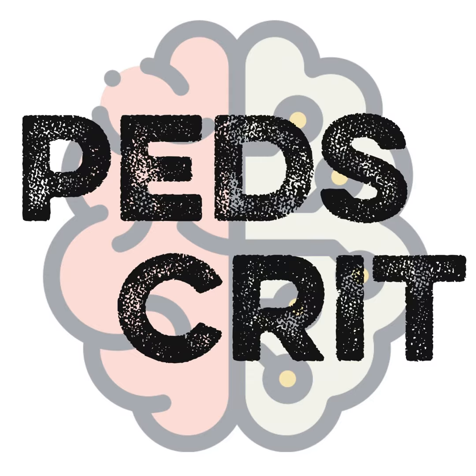So if you nebulize things like mucomist or DNase or antibiotics, all of those things, the diluent tends to be in glycerol. And glycerol tends to be sticky. And a device that's supposed to slide with minimal friction, that doesn't go well together. So patient with cystic fibrosis, you're trying to do mucomist and pulmozyme, and you need them on the VDR. Our standard is that for a patient that's not getting any nebulized meds other than saline, we change the phasotron out every 3 days. If we're adding then a nebulized medication, we change that phasotron out every day, if not sooner than that, based on what it looks like the phasotron is doing.